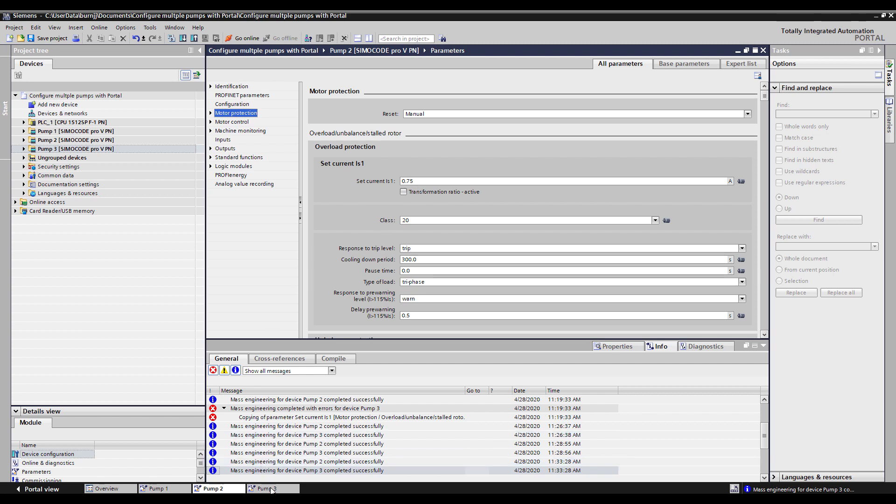And if I come to pump three, that one also has been changed to 0.75 and a Class 20. So just that quickly using the Expert List and more specifically the Mass Engineering function, we can change multiple parameters on multiple SIRIUS Controls very quickly within the TIA Portal software.